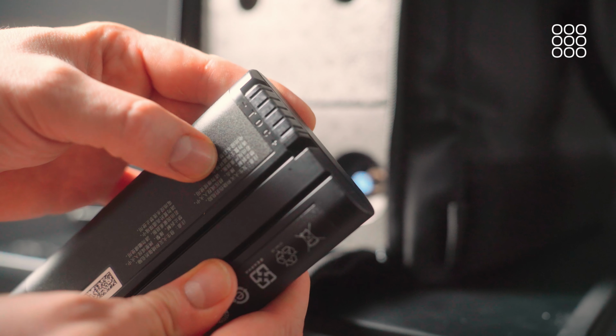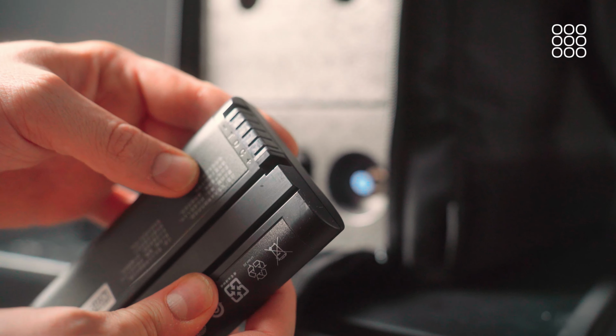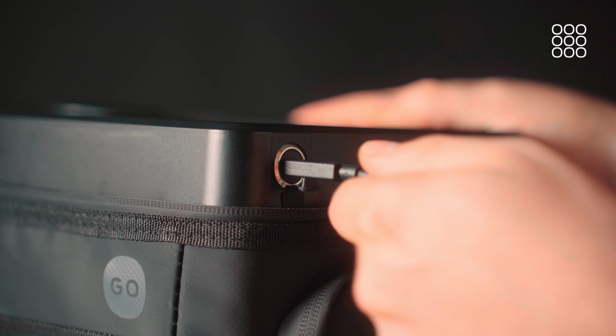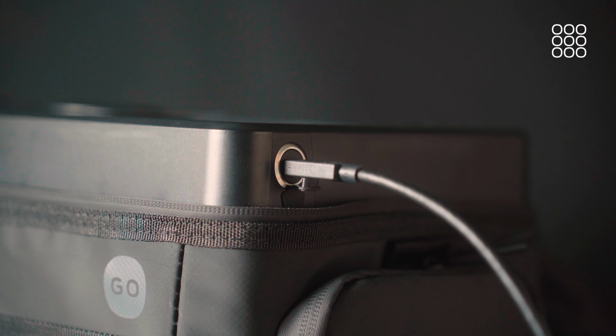The Cellbox Go relies on an internal battery for power. To ensure safe operation, you should always check that the battery is fully charged before starting a transport. If the battery is being replaced during transport, ensure clean and intact pins for proper connection and function. The USB-C port on the right side of the device is used for charging, and it's important to ensure that all power connections are dry and intact to avoid any electrical hazards.